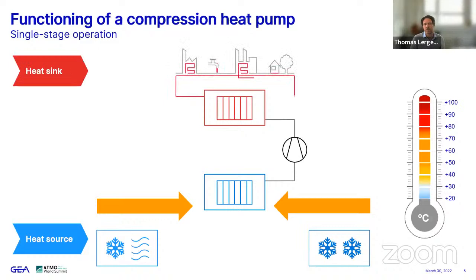And while liquefying, it rejects the heat to a heating cycle that provides any heating demand there is in the industry, process heat, facility heating, that is called the heat sink. And after the refrigerant has liquefied and rejected the heat to the consumers here, it is expanded again to the lower pressure and lower temperature level, where it can evaporate again, and then the whole cycle starts anew. So here, this is an example where this heat pump sucks up waste heat from industrial processes, from air conditioning, cooling devices that also emit heat.